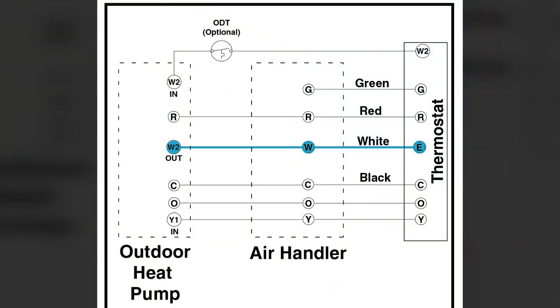And it's used for when the heat pump is not working. Let's say it's froze up because it's not defrosting. So you instruct the homeowner, okay, turn it to emergency heat. That'll give you heat until we can come out and take a look at the heat pump and find out what's going on. All right, so now we're going to go back to W2. W2, what is that? W2 is essentially auxiliary. So in regular heat pump heating mode, you essentially got 2 stages to the thermostat. Your first stage is the heat pump, which is Y. That turns on the heat pump in heating mode.